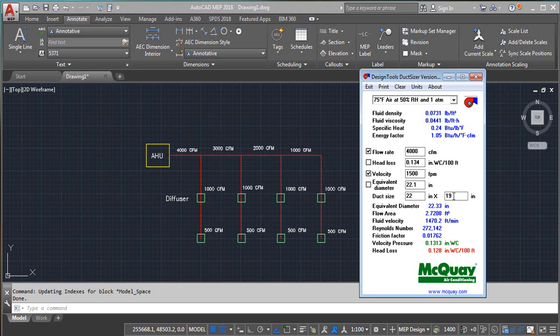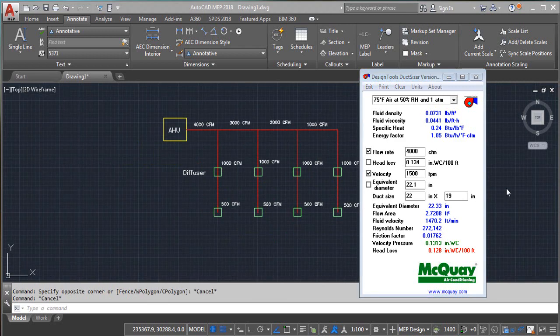The height will be 19 inch. And always choose even numbers. So the nearest even number to 19 is 20. Don't choose 18, but choose a bigger number so as to be on the safe side. Now the size of the main duct will be 22 by 20 inches, and write the bigger dimension first.